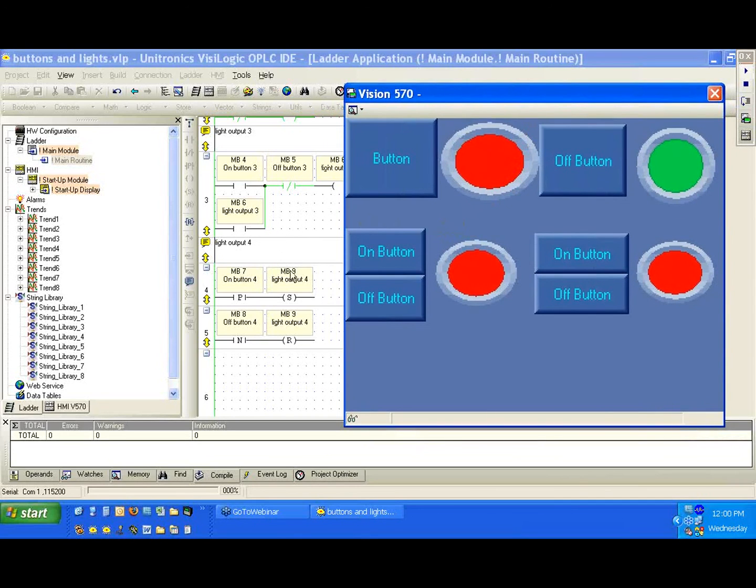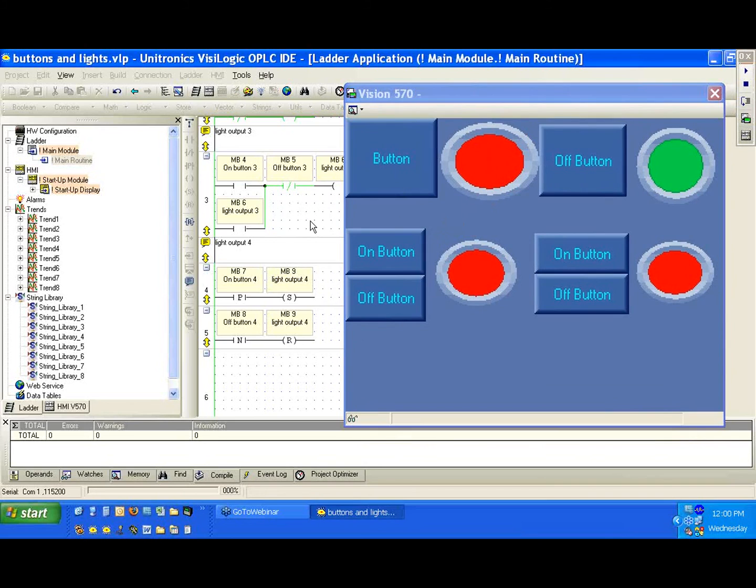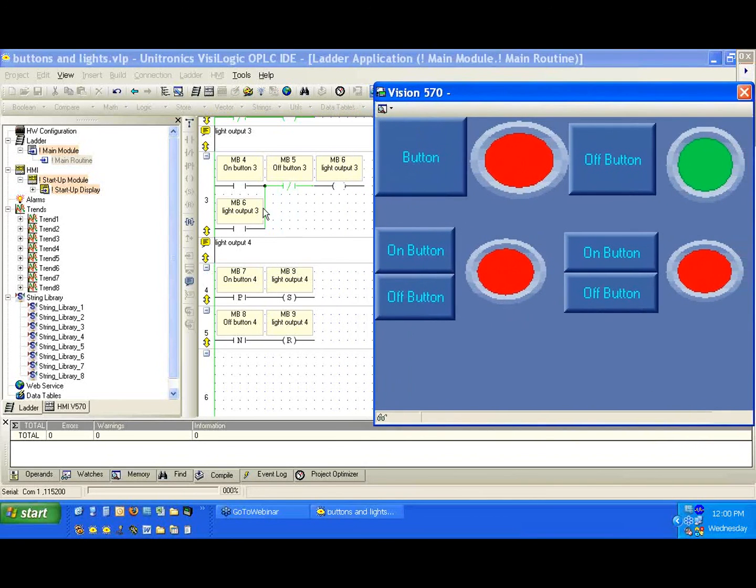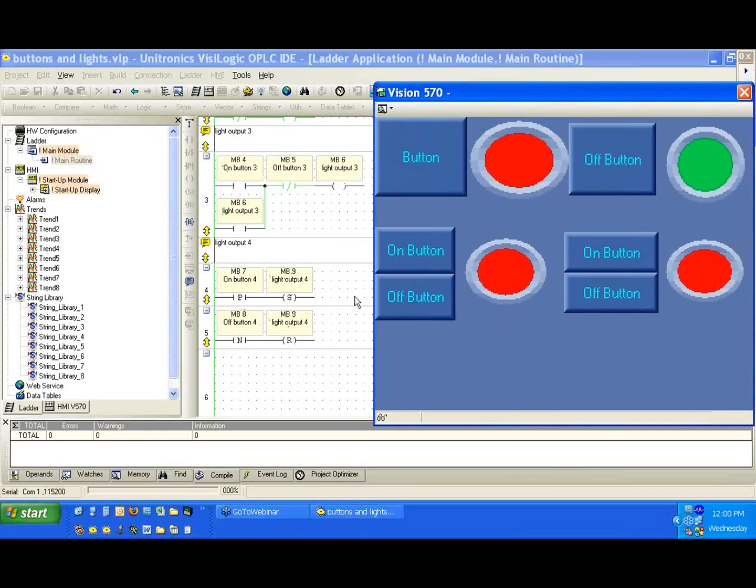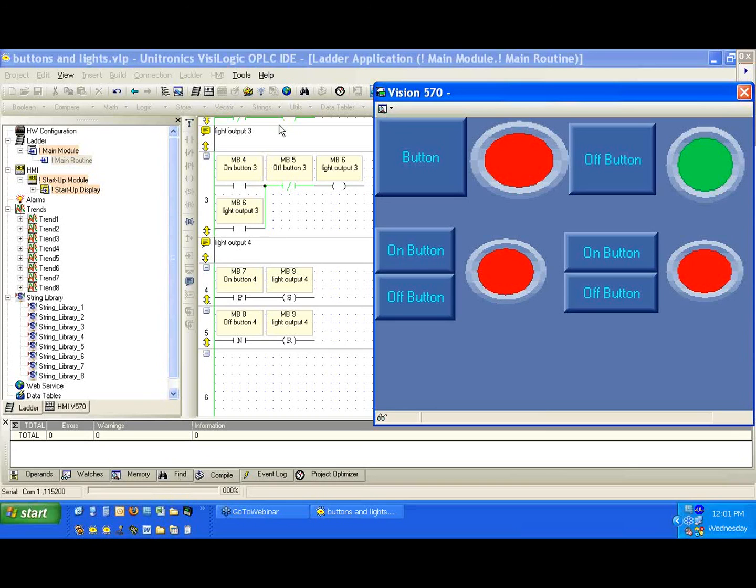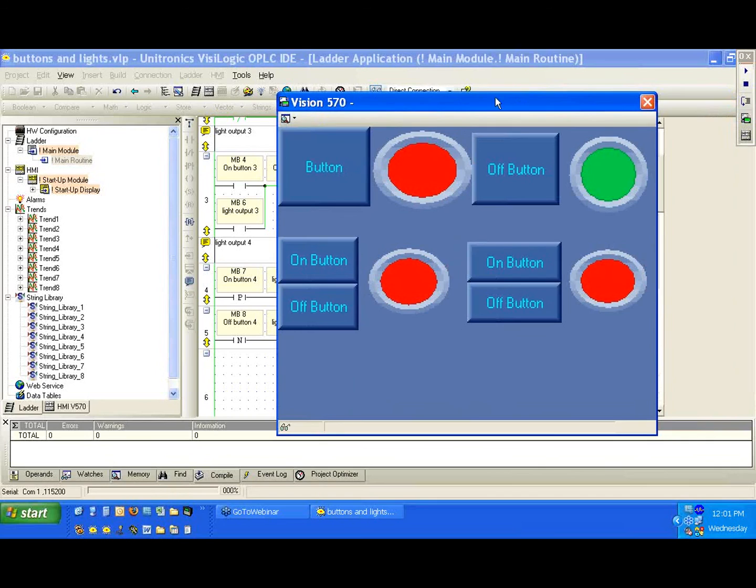So one point is also that there are many ways to do things in the ladder logic. The nice thing is that because we have a more advanced operating system than we did comparing to relay logic programming, we have this set and this reset where we can set and reset a bit and it'll maintain its state until we come and influence it again. The idea of the single scan transition is very important. Also the idea of the program scan is very important.